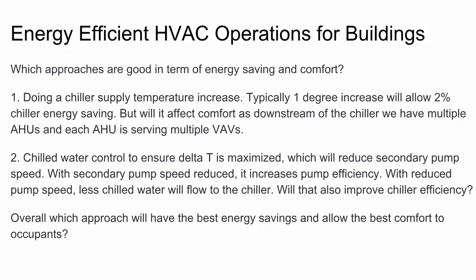One, doing a chiller supply temperature increase. Typically 1 degree increase will allow 2% chiller energy saving. But will it affect comfort as downstream of the chiller we have multiple air handlers and each air handler is serving multiple VAVs? Great question.